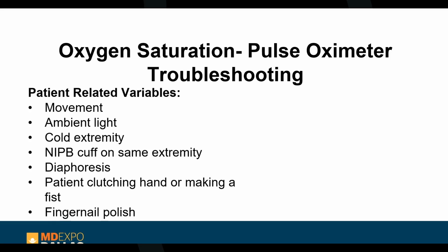Everyone that's worked in biomed very long has probably seen this one. A non-invasive blood pressure cuff on the same side as the pulse oximeter. So if I have the cuff on my left arm and the sensor on my left finger, when the cuff pumps up, it stops that blood flow. So it's going to intermittently read bad, right? Every time it inflates, it's going to read bad. That's maybe one you almost have to see to say it's operator error. And usually nursing people catch themselves.